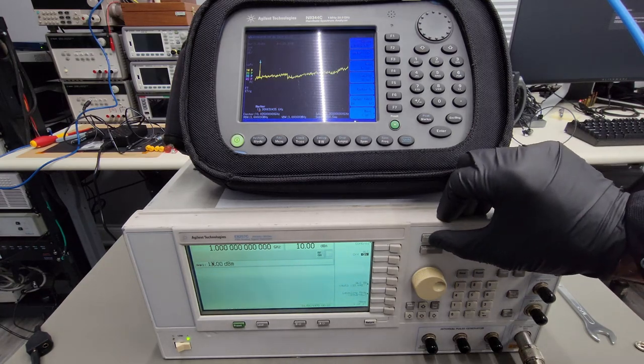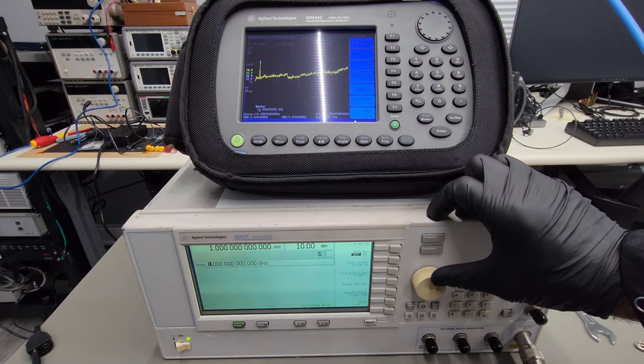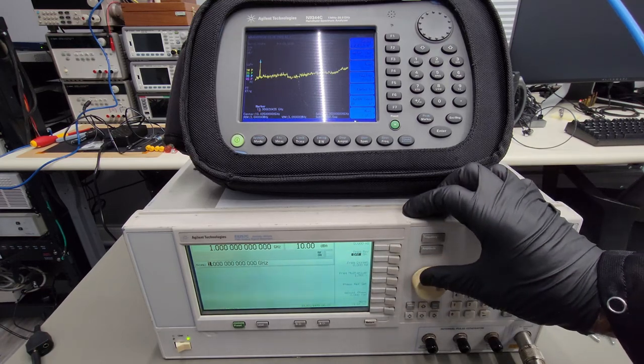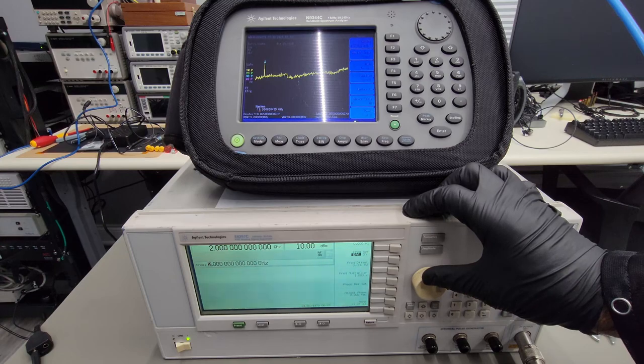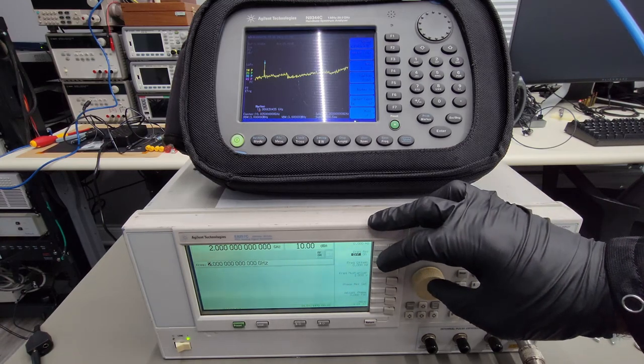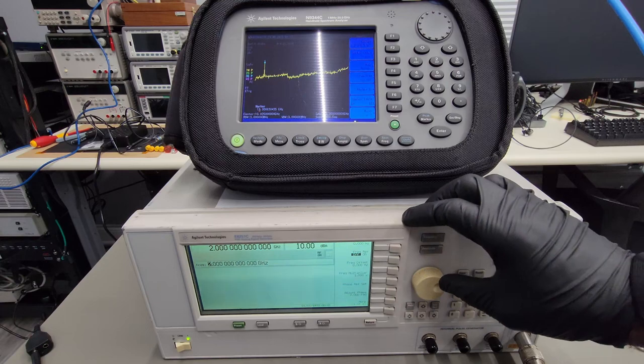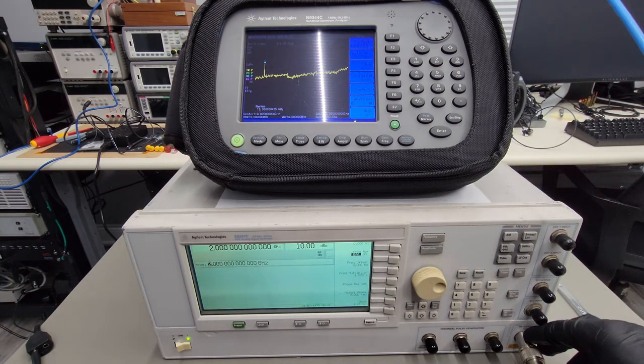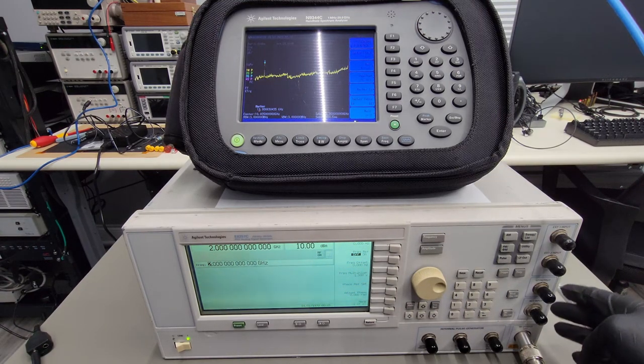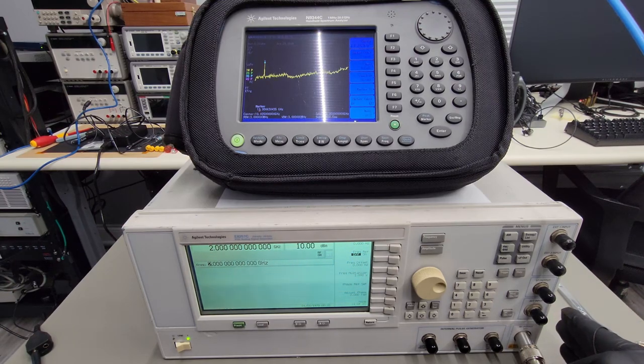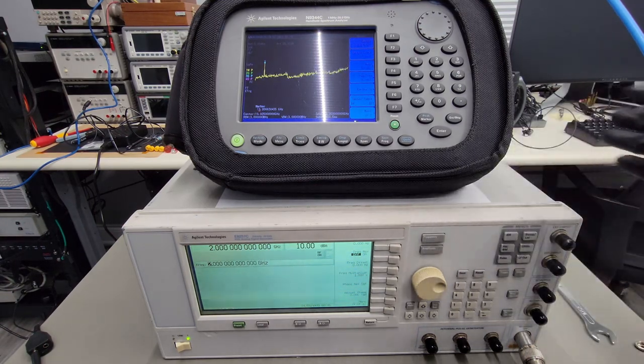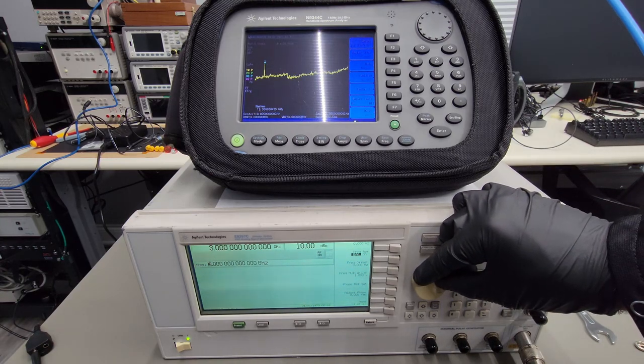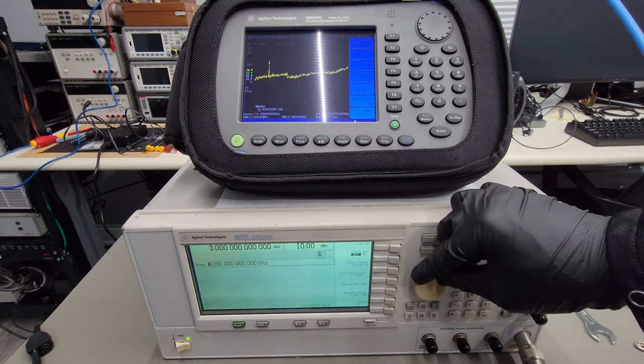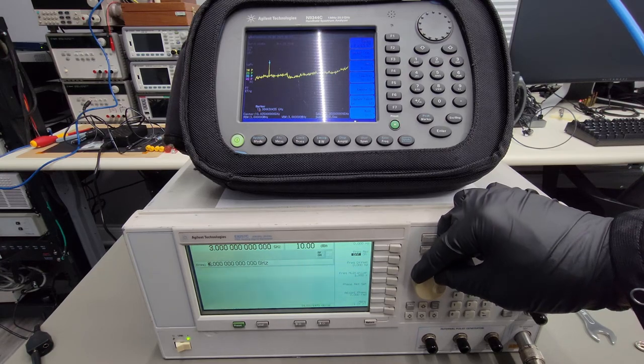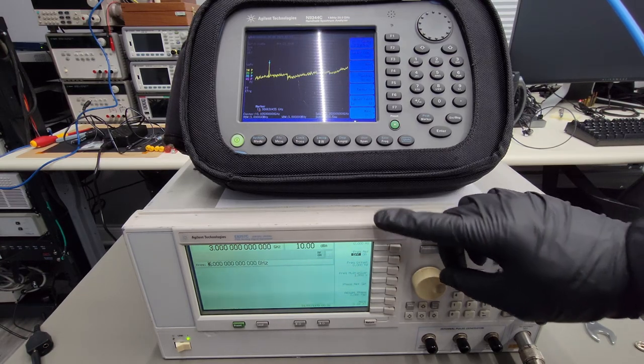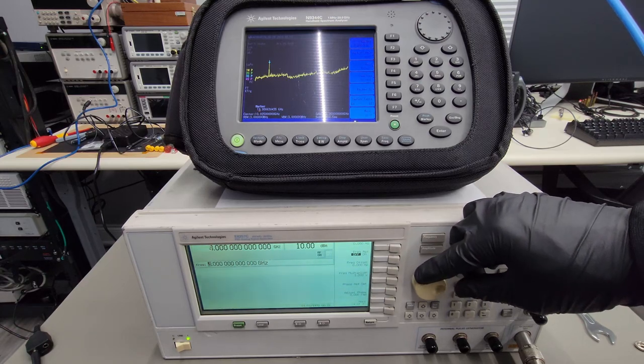Let's just go up in frequency a little bit and see if we see any unlocks or unlevels or anything else going on. You know, the generator isn't reporting an unlevel, even though our power is really low. Now it could be a damaged semi-rigid cable inside of the unit from when this front panel connector was impacted. It could be a lot of things. The power seems to be pretty flat though. It's around minus 20 dBm for the same power setting on the signal generator.